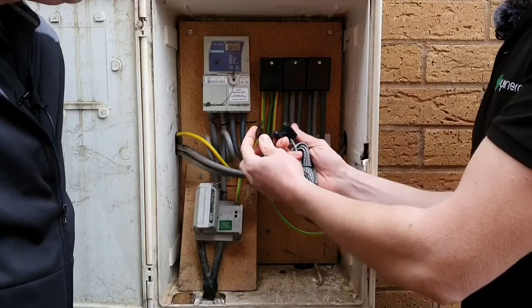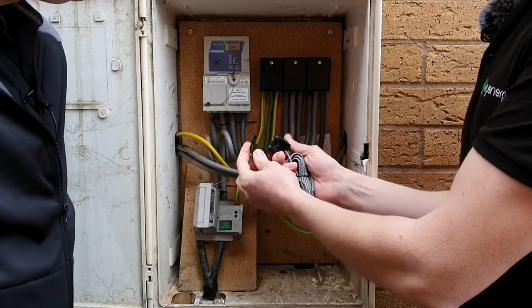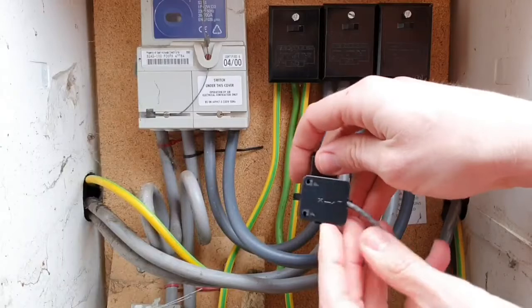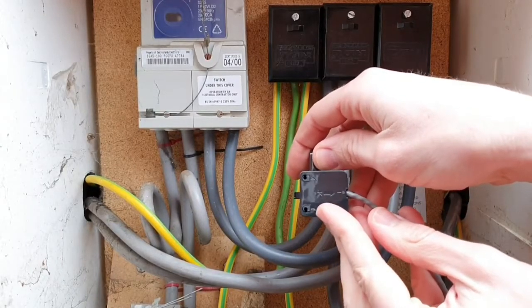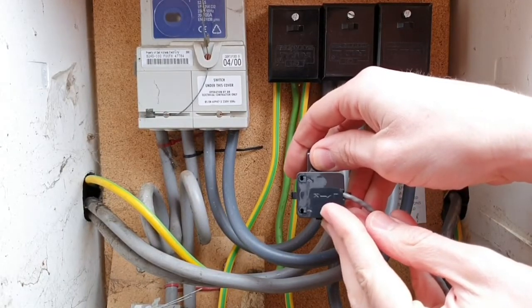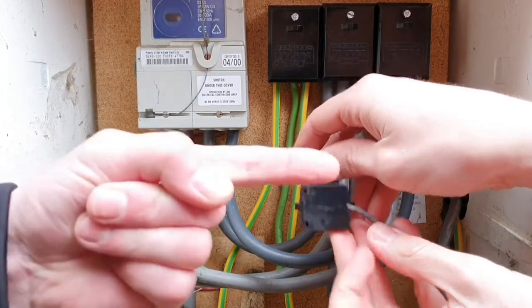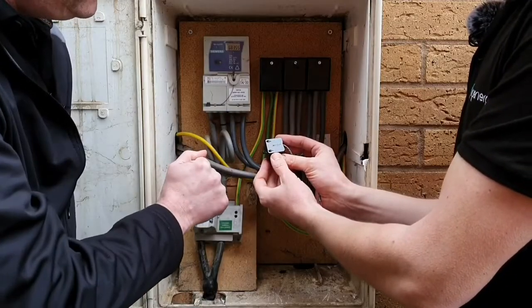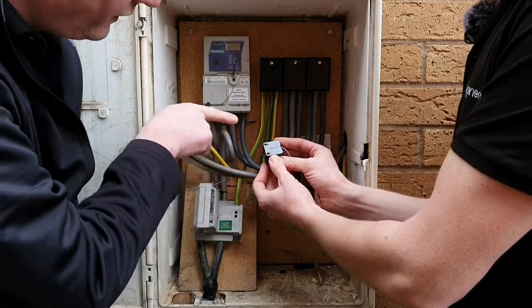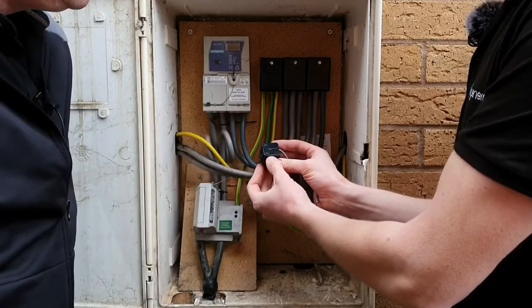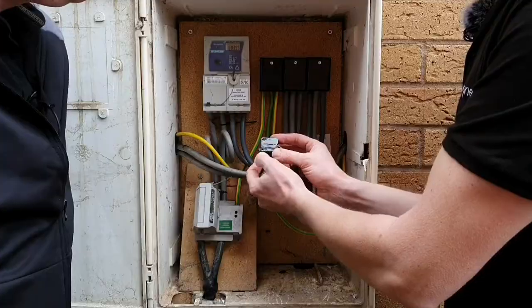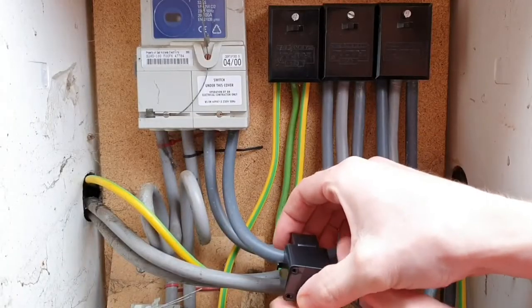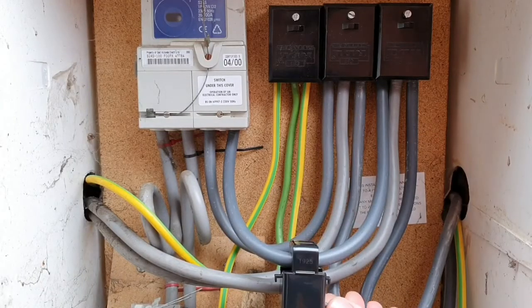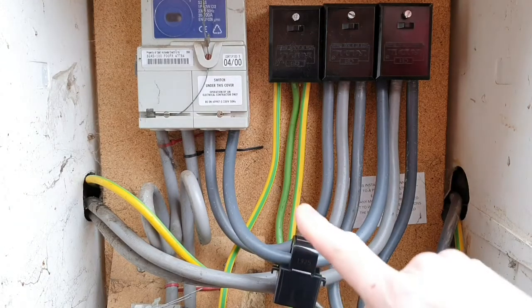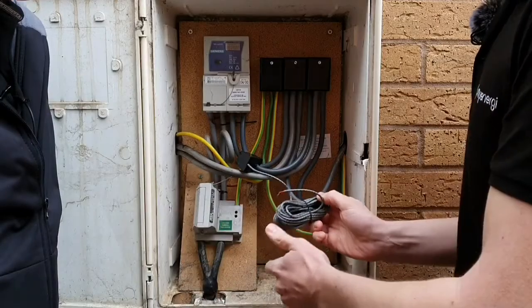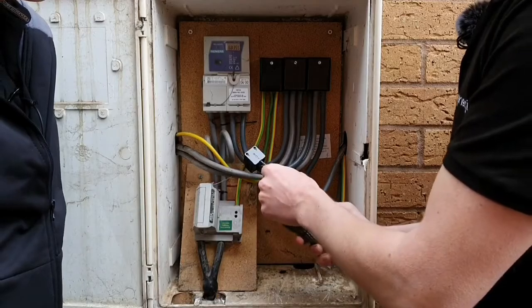But there's one other thing, and this is absolutely critical at this stage, Gary. What do we need to do here? We need to make sure its direction is correct. In other words, we're going to measure the current coming into the installation, and we've handily got an arrow pointing that way, and that's the way in which we need to clip it on in order that we can get the current coming into the installation. Absolutely. So you can see there's an arrow on the bottom of it, and we want to get that, as you say, around the line conductor into the installation. So that is now going to measure the current that's flowing into there, and we can wire this across to our Zappi charger as well.